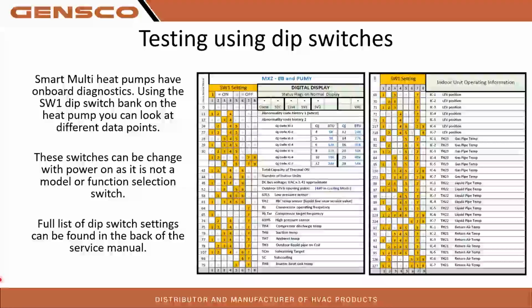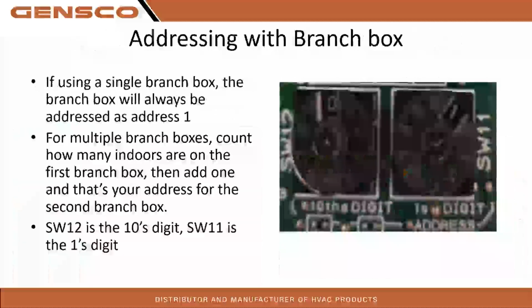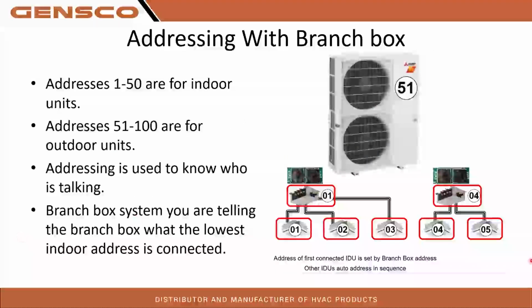Looks like Vlad had a question: how would you address the dials on branch boxes, one a 5-port and the other a 3-port? So again, if you have 2 branch boxes, one of your branch boxes is always going to be address 1. For your second branch box, count how many heads are on your first branch box. If you have 3 heads, just add 1. That would be your address, address 4.